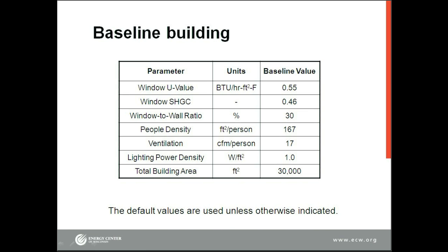You can use the sliders to input these values. Specifically, the window U-value needs to go to 0.55, so you can just click on the slider and drag it to that value. Similarly, the values for solar heat gain coefficient, window-to-wall ratio, people density, ventilation rate, lighting power density, and overall building square footage need to be updated. You can also enter these values directly into the cells that are controlled by the sliders. This is particularly useful if your values are outside of the range of the sliders. However, be careful — doing this will potentially result in a loss of functionality of the sliders, as well as the reset to defaults button. I would recommend always starting from the same saved template of the back-of-the-envelope calculator, and never from a version that you've already changed.